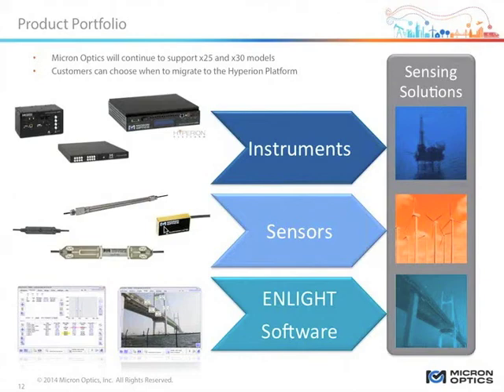Where we have seen some areas for improvement in durability and quality has been in the overall instrument architecture itself. I mentioned a little bit earlier about there being 5 different boards in the SM125 or the SM130. And frankly, where we've seen the vast majority of our field failures have come in board-to-board connectors. These are power distribution cables or signaling cables, things that can be susceptible to shock and vibration over time. So what we've done in this instrument is design all of those out. The electronics, the data processing, the data capture is all within a single PCB design. All routing of electrical signals, be they signal or power, is happening within this sandwich multi-layer board. So intrinsically, that's going to lead us to a more reliable, mechanically more reliable solution.